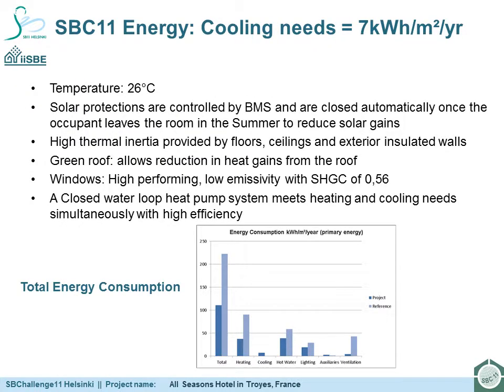The thermodynamic simulation was used to reduce cooling demand. Interior solar protections were found not to be effective. However, exterior solar protections prevent solar energy entering the building, thus reducing the cooling needs. This hotel has applied for the French energy efficiency label HQE Environmental BBC, currently the most stringent in the country. Using the French national calculation methodology, or RT 2005, the energy consumption for the heating, cooling, hot water, ventilation, lighting and auxiliaries was estimated at 110.7 kilowatt-hours per metre squared per year in primary energy. This is over 50% less than the required energy consumption level. For the heating demand, the amount is estimated at 37 kilowatt-hours per metre squared per year in primary energy, and the cooling demand is estimated at 7 kilowatt-hours per metre squared per year in primary energy.